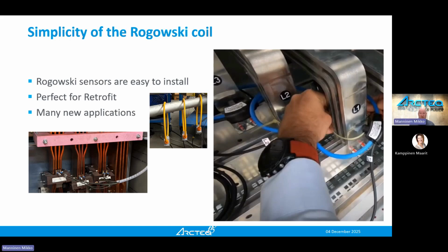Many times in installations, the scheduled time for the outage can be very limited. I have done a lot of retrofit installations where they gave us 8 hours per day, and doing all the paperwork took 4 - because you need to do the paperwork when you get the board for the job and when you return it. So from an 8-hour window, you have 4 hours to do the job. Maybe you've faced the same thing in your installations, but this is very typical if the plant or site is something critical.